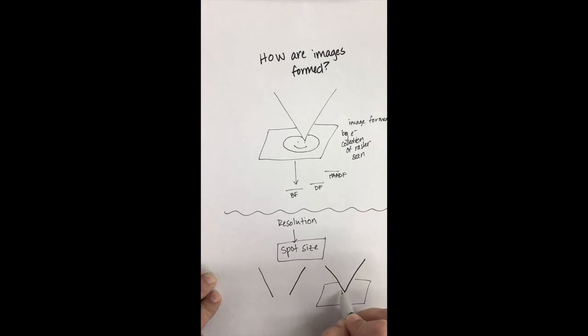If the beam is focused to a very fine point, then each position in the raster scan will be relatively small and therefore close together. If the beam is focused widely, that means less spots collected across the sample and a poorer resolution.